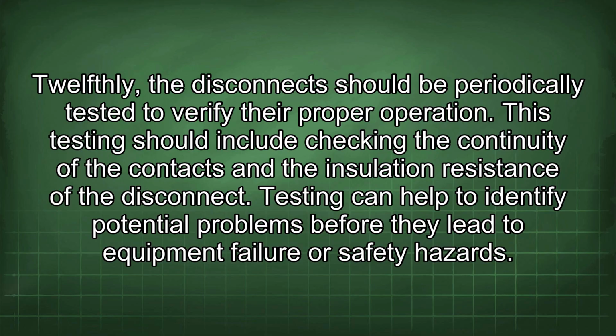Twelfthly, the disconnects should be periodically tested to verify their proper operation. This testing should include checking the continuity of the contacts and the insulation resistance of the disconnect. Testing can help to identify potential problems before they lead to equipment failure or safety hazards.